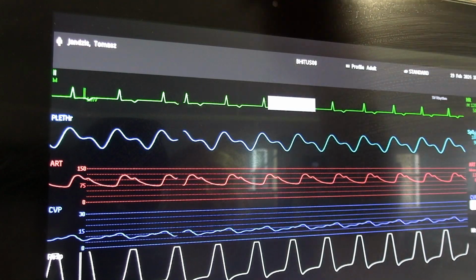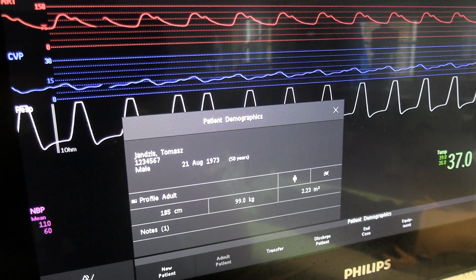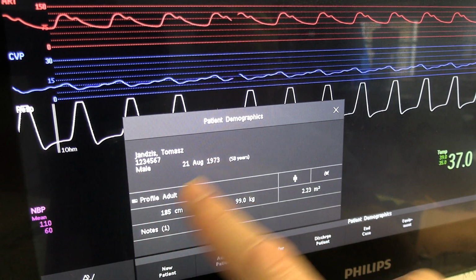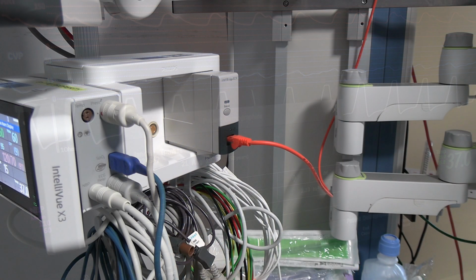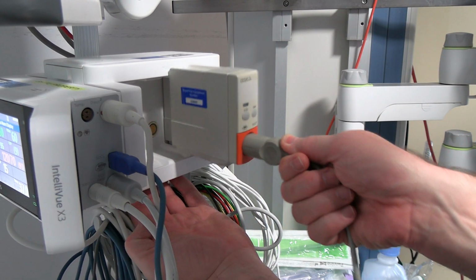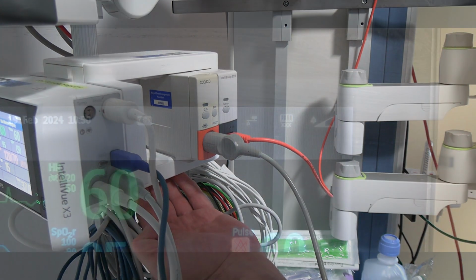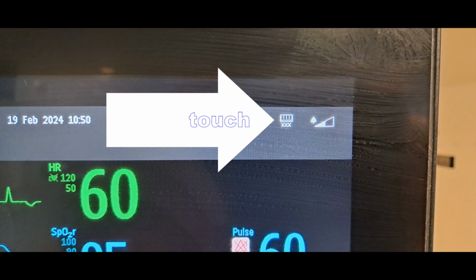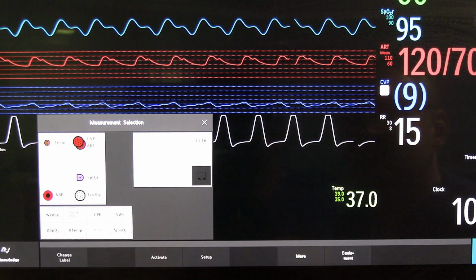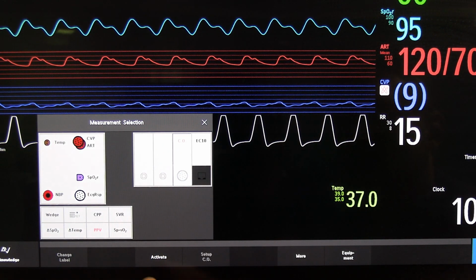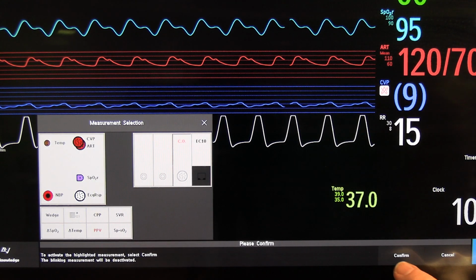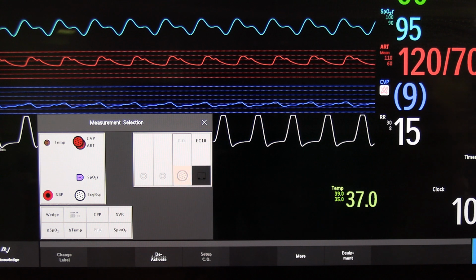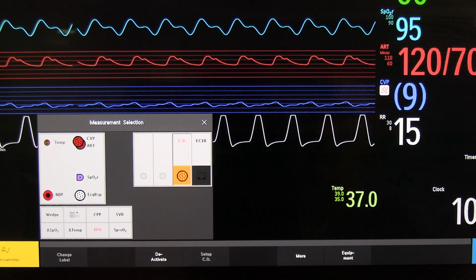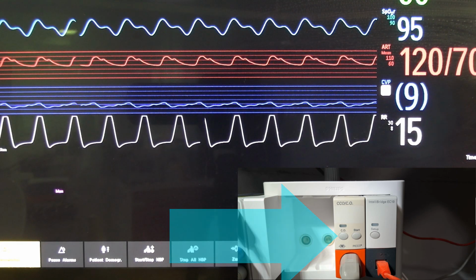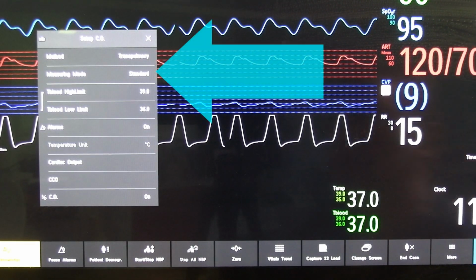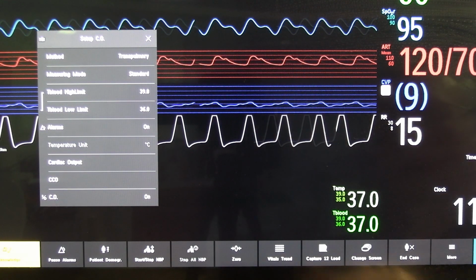Begin by checking the patient's admission details on the monitor. For further calculations, we require gender, height, weight, and date of birth. Next, insert the PiCCO module into the holder and wait for 20 seconds for activation. Then, navigate to the devices list and verify if the module is activated, not grayed out. If not, please press Activate. Press the CO button on the module, and within the menu, select Auto Mode to avoid touching the screen during the tests.